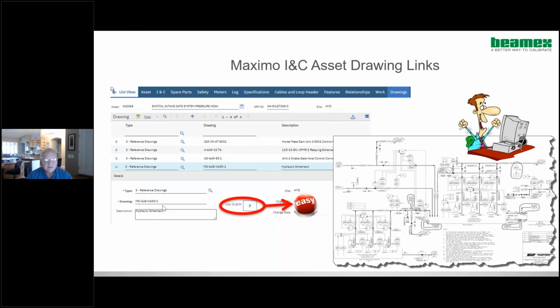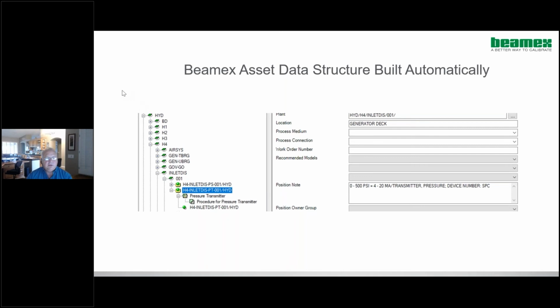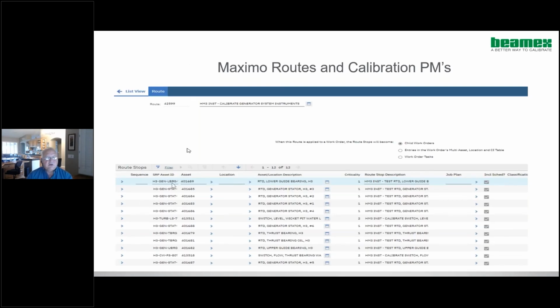They add the print, and it automatically loads into our document management system, builds this link for them. So this system works like a champ. When it goes over to Beamex, if the unit's not there, it will automatically build it for you. If the system's not there, if it's the first point, it will build it for you. Then it will build your instrument number, and then you have your point. We have to go in and set a couple parameters off of this information, but then it's built. Now in Maximo, this is called a route.